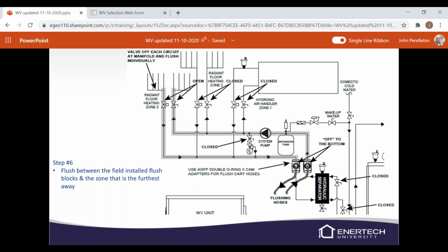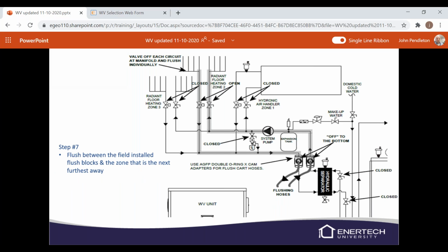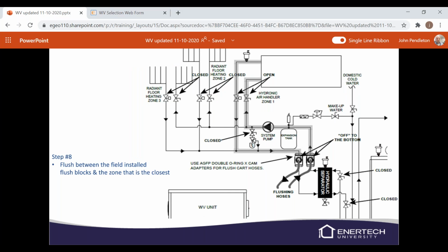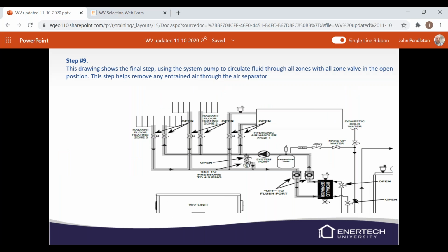Then we're going to flush through your furthest away zone. So close off your bypass circuit and flush through your farthest zone away. Then your next farthest, and then your next farthest, and so on until all the zones are flushed. Then go ahead and open up all your zones and flush through it all. Go ahead and open up your bypass at that point, and we're just going to flush that whole circuit again real quick.